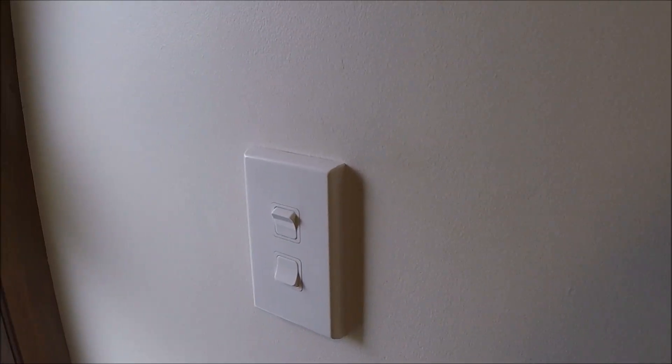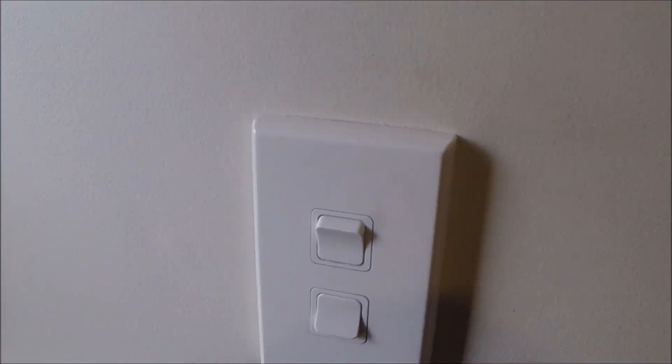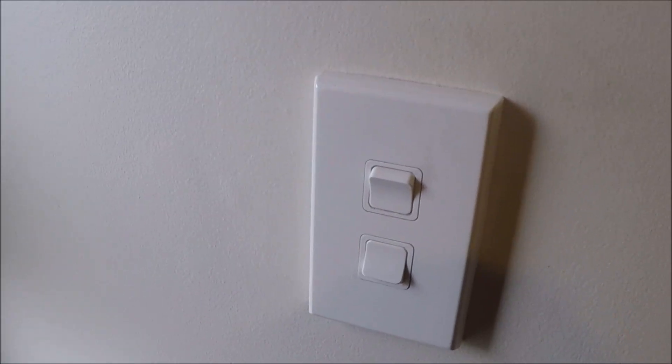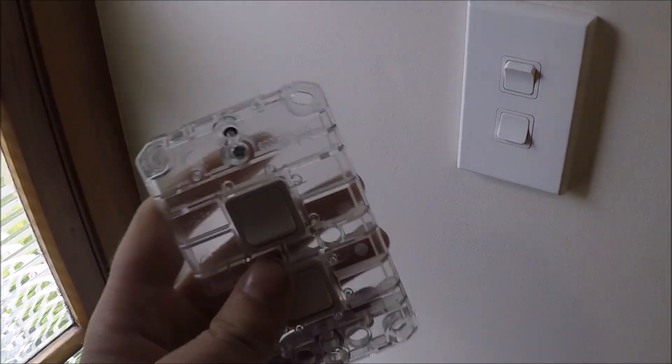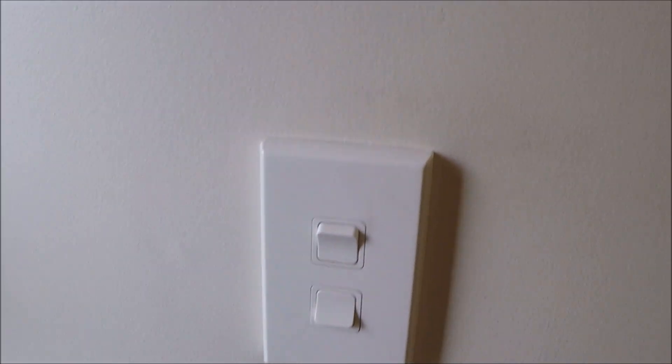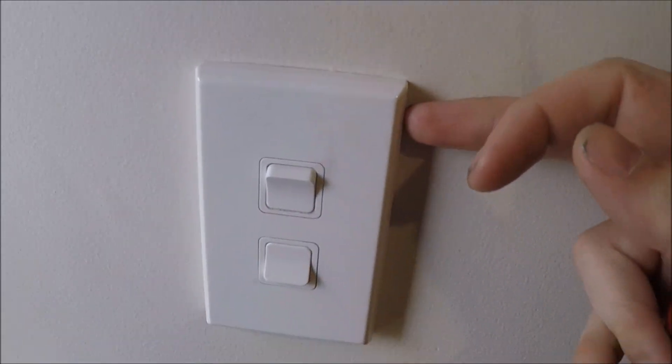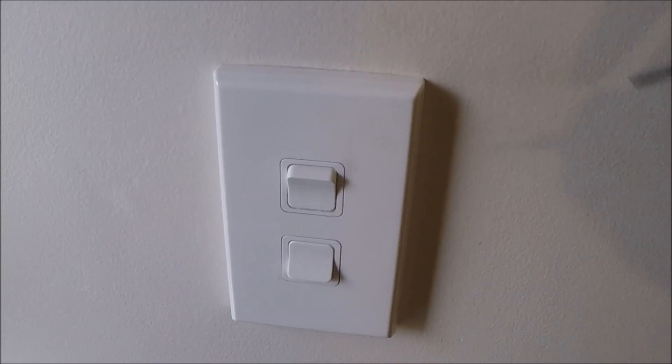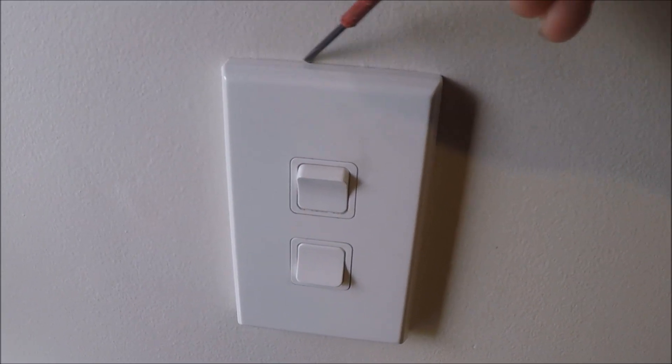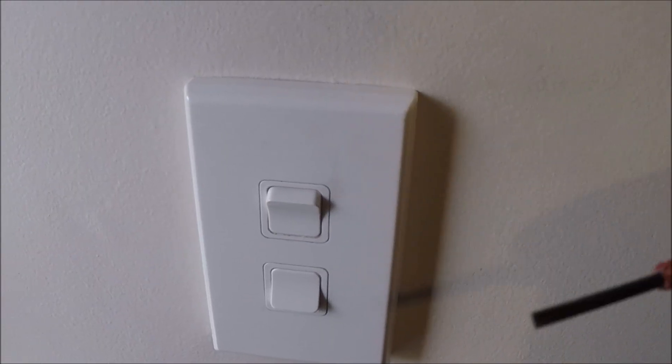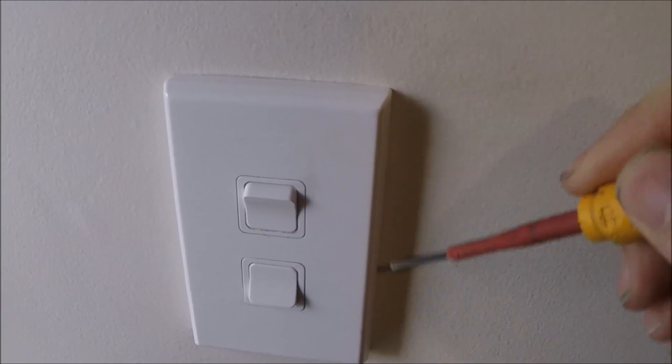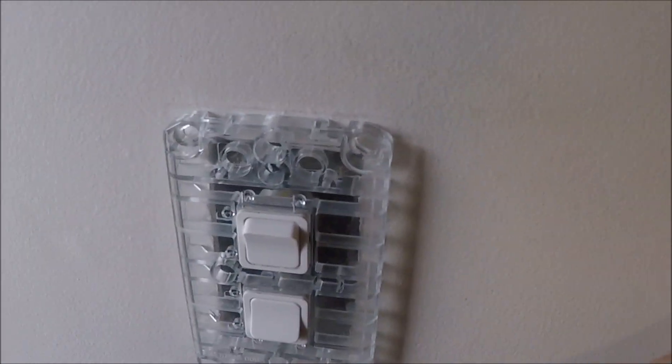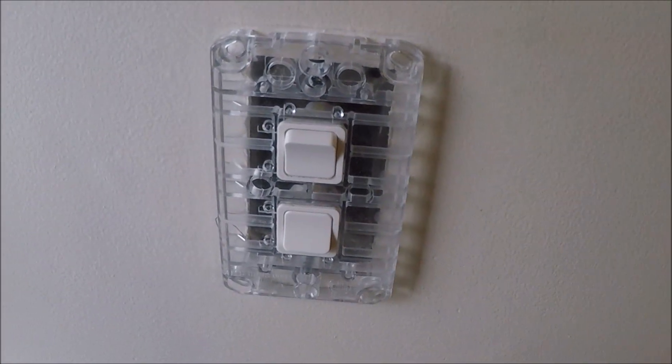Okay guys, this video is going to be how to replace a two gang switch. I'll be replacing it with the same switch, 600 series PDL. First thing you want to do is take the cover off. Be careful of some of these because some sparkies leave them on and the painters paint around the outside, so you might want to run a knife down the edge or side of your screwdriver and then peel her off.